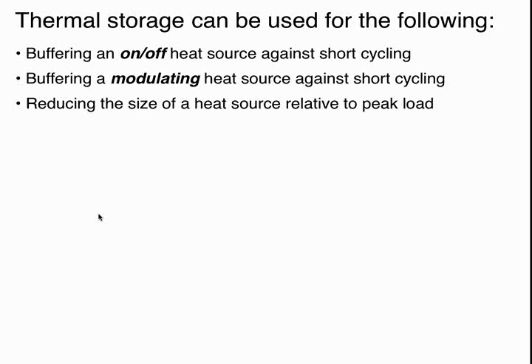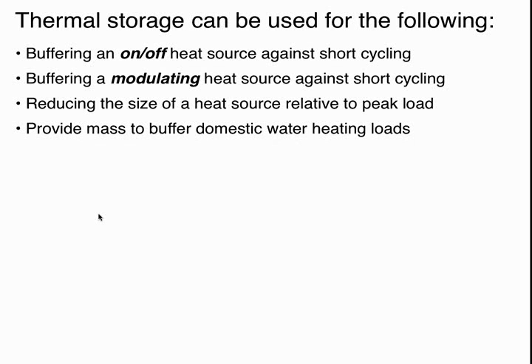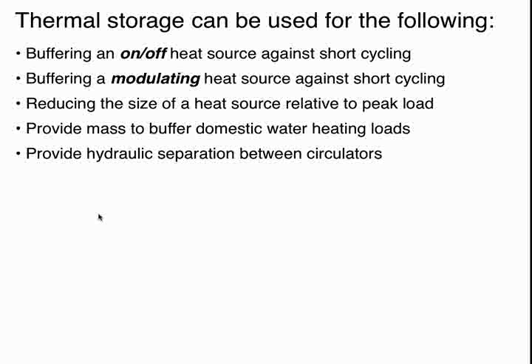Thermal storage also lets the rate that we can deliver heat to the load be substantially different from the rate that the heat source produces heat. In the case of a transient load where we need a lot of heat in a short period of time, our limitation is just how fast we can bring the heat from storage to the load. It's not how fast our heat source can generate heat over a short period of time. We can also use the same thermal mass that buffers space heating to buffer domestic water heating loads. And we're going to show you some details for that.